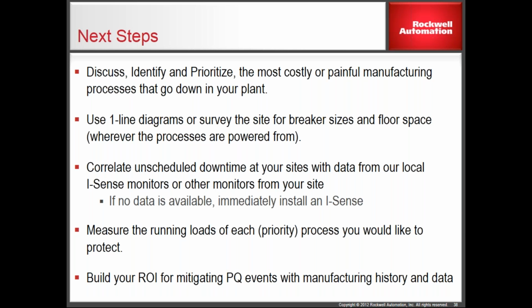And then finally, if you're down to the point where you want to do something, measure the actual running loads. Because one of the things we're famous for in industry, right, is we oversize. So we're going to put a 400 amp breaker on this side, and we're going to feed that circuit, and boy, we're going to be good, because when you actually measure that circuit, it's drawing 57 amps. You go, okay. And the way the DySC is designed, I can pull startup current through it. I can pull 150% of its rating for 30 seconds. I can pull 600% of its rating for half a second, a linear equation between.